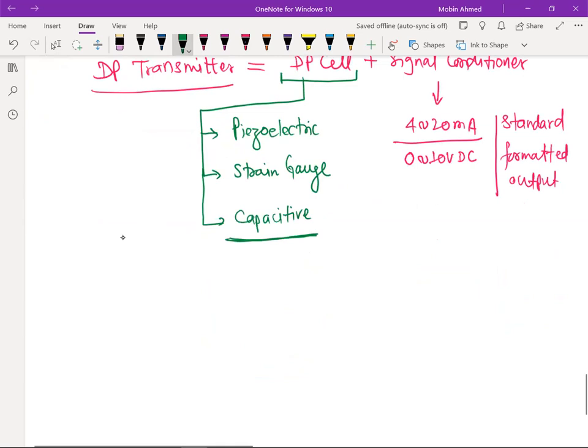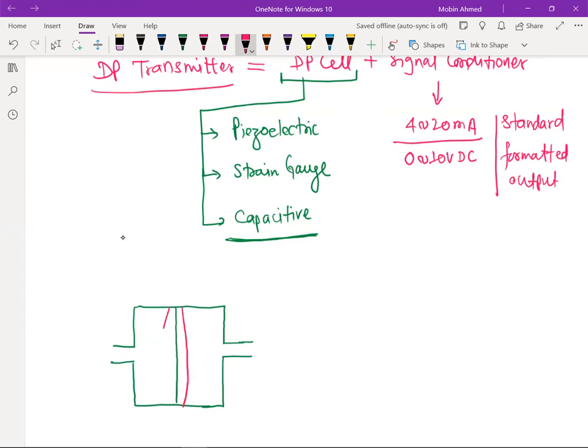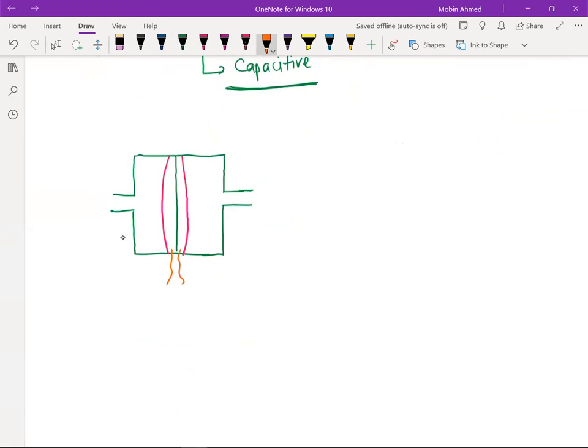Now, whichever cell the DP transmitter uses, it is going to have two pressure lines connected to it. Suppose we are using a capacitive type, like this. The output we can take from here, this is the wire where the output will be. This gives a difference in electrostatic charge, as this is the capacitive type, and as per that it gives the output. This is going to give 4 to 20 milliamp. It means after the DP cell, it goes to the transmitter, and the transmitter gives this output. The DP cell does not give the 4 to 20 milliamp.